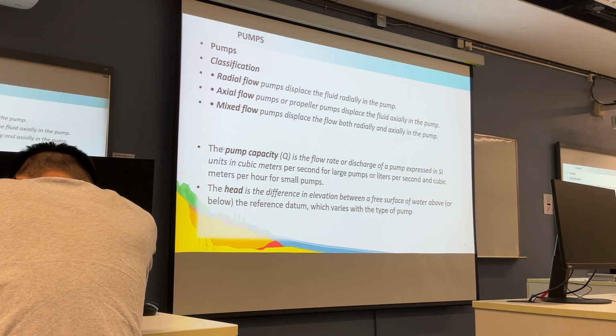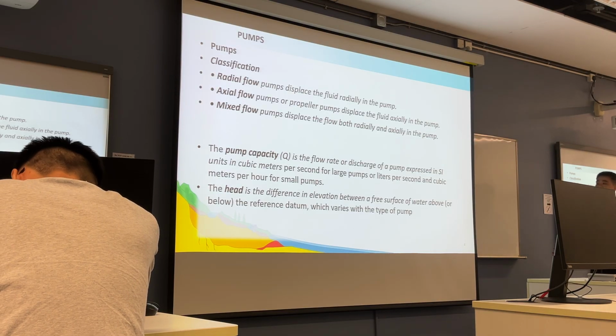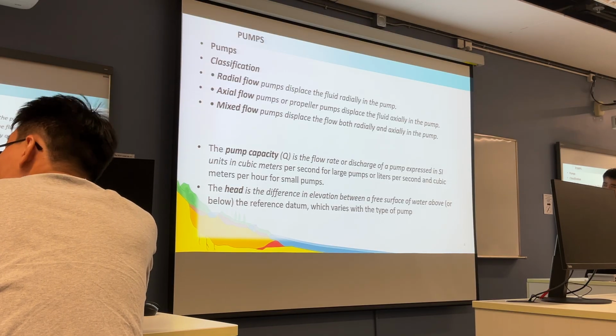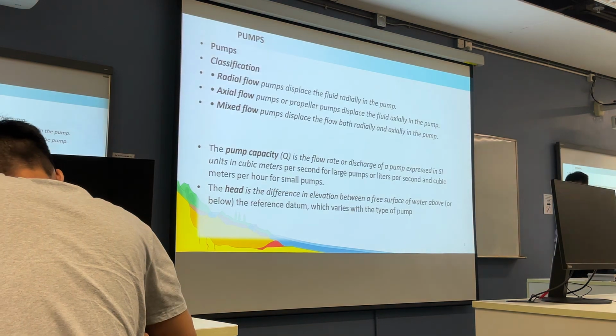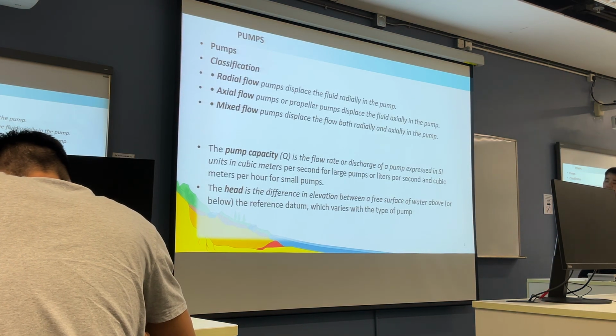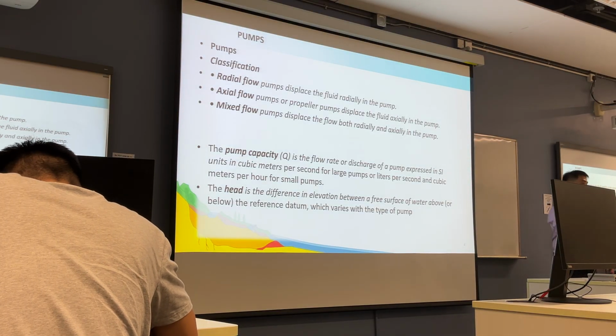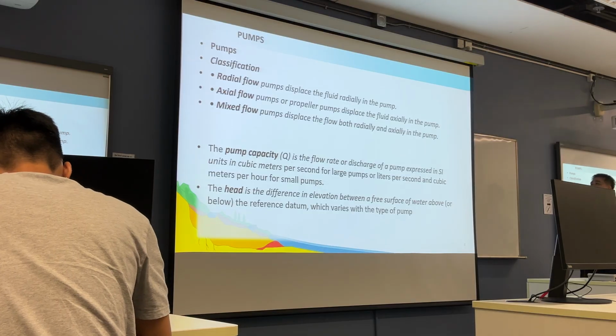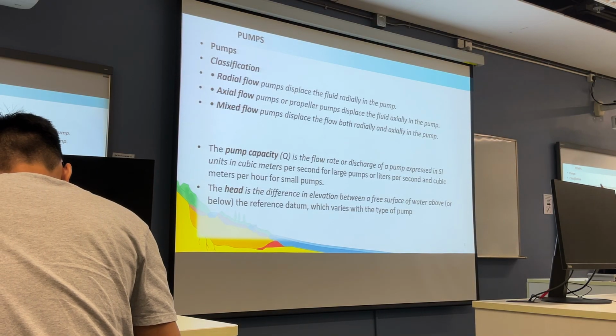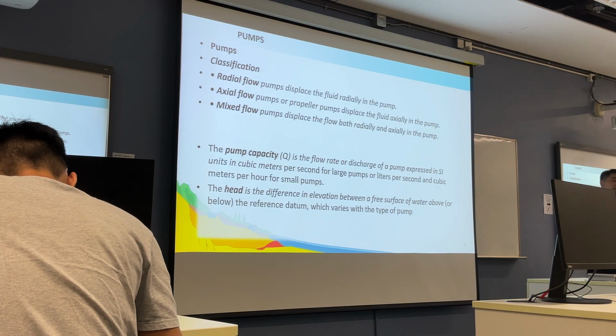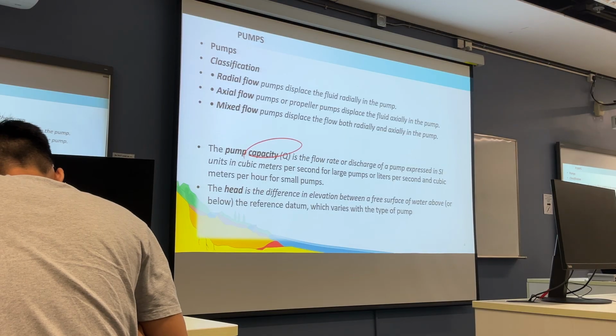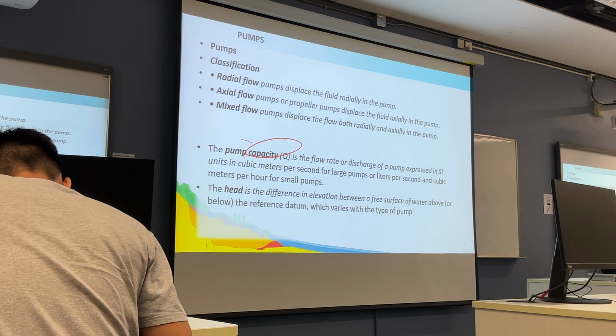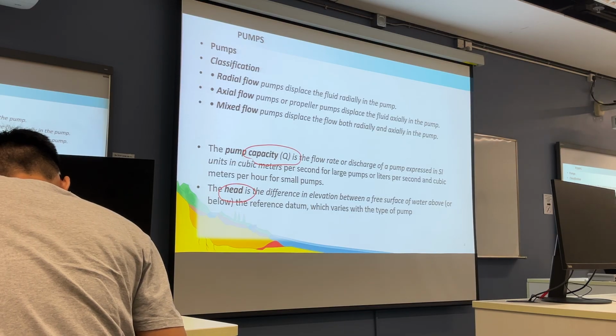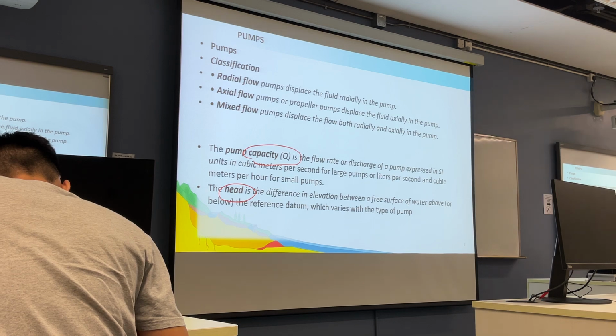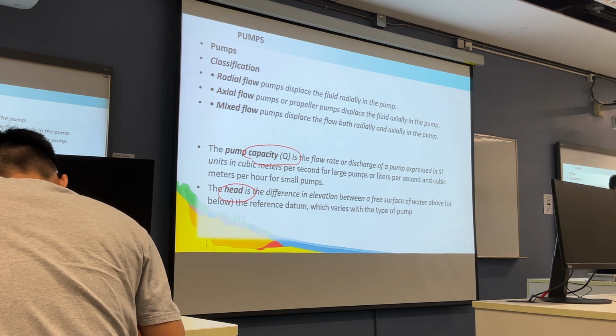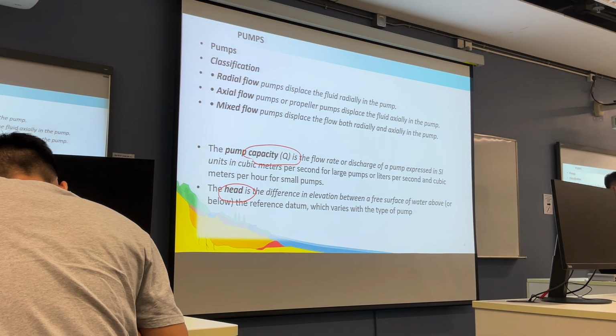Now, for the pump design, or we say the pump selection, okay, because we are not talking about mechanical engineering, we are not manufacturing the pump, but when you are doing the calculation or engineering the pump system, you may need to select the type of pump from the supplier, okay. So you may mainly focus on two things. One is the pump capacity, which means the discharge, okay, the discharge. And another thing is the pump head, okay. One is the pump discharge, another one is the pump head. These are the two main things that you need to consider as the parameters to select the pump.